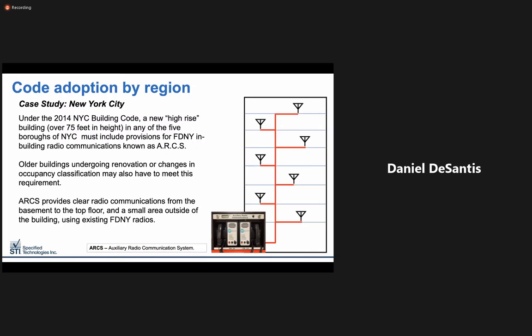The specialized hardware required for an ARC system provides on-site command and control throughout the building. ARCs provide clear radio communication from the basement to the top floor of the building, and some areas outside, using existing FDNY radios. Only the FDNY is permitted to operate the ARC's controls. The auxiliary radio communication system uses a building-specific antenna combined with a low-powered transmitter and receiver. An engineer custom designs each antenna system to make sure that it's balanced with consistent and adequate radio coverage.